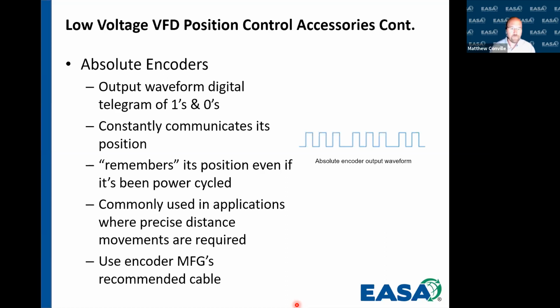It's very commonly used in applications where we need to move an extremely precise distance, or we're wanting very precise speed control where it needs to constantly communicate. These encoders, again, much like the resolvers and the incremental encoders, we want to follow the manufacturer's recommendation for cabling, and the cabling manufacturer's recommended practices for grounding, so that we don't have any noise.